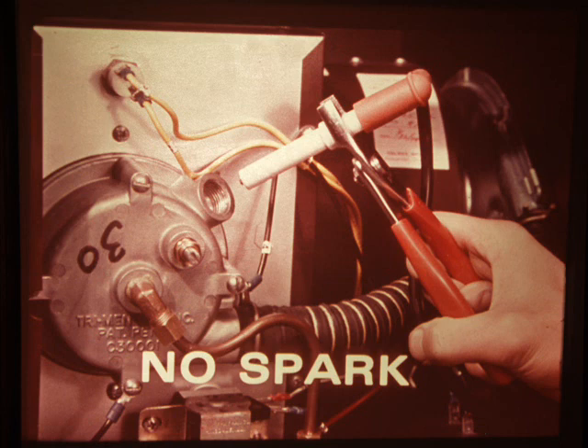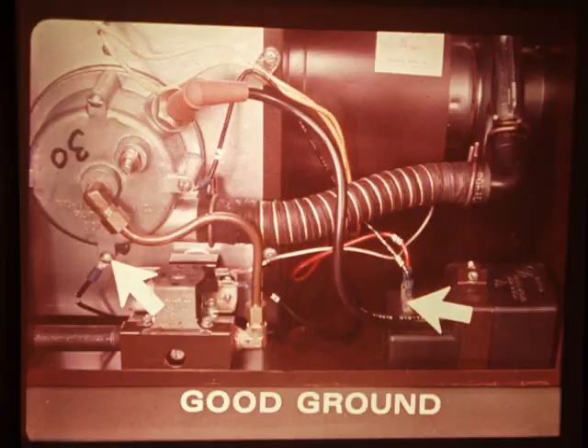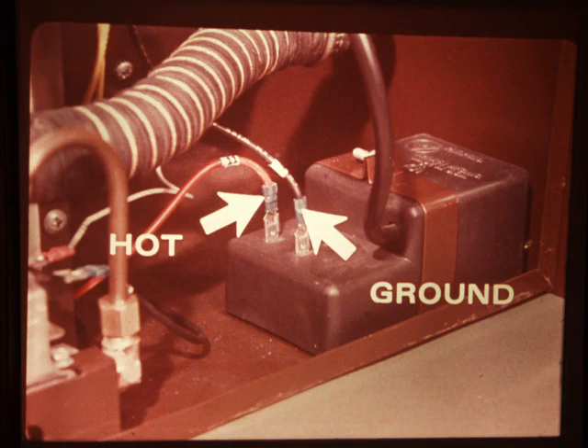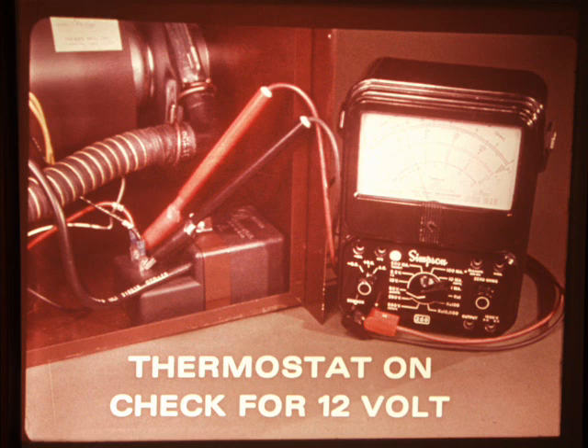There are several checks that can be made with the furnace installed. First, be sure the ignition pack ground wire has a good connection at both the ignition pack and the burner housing. Also, check for proper polarity at the pack. The red, hot wire must be at the left, and the black ground wire at the right. With the thermostat on, see if you have 12 volts at the ignition pack. If you don't, pull the furnace for bench testing.